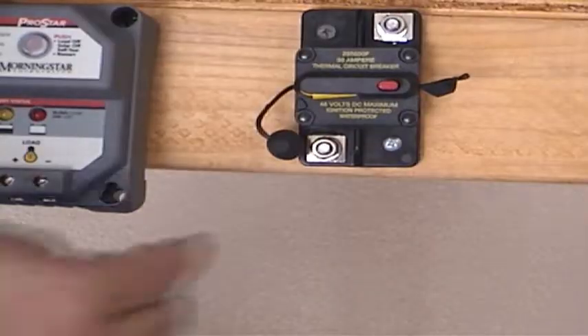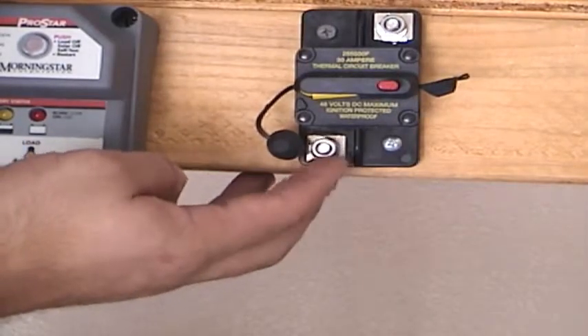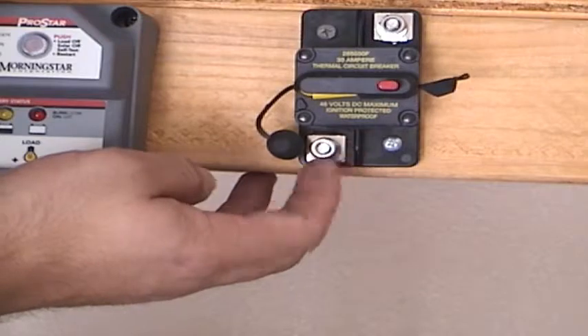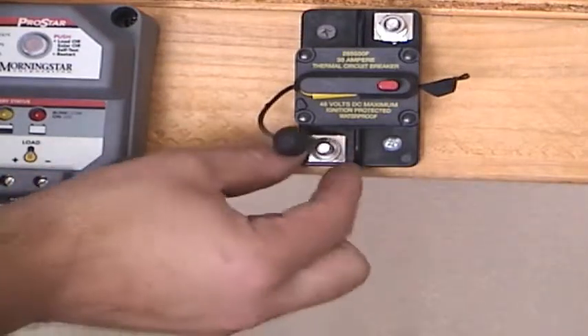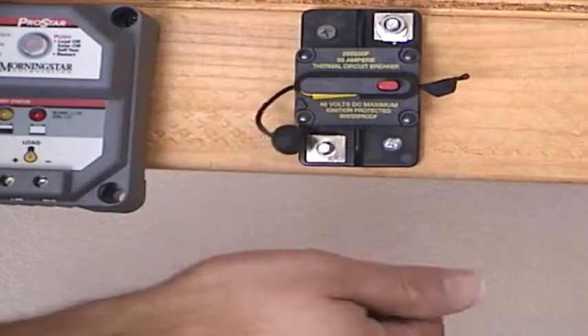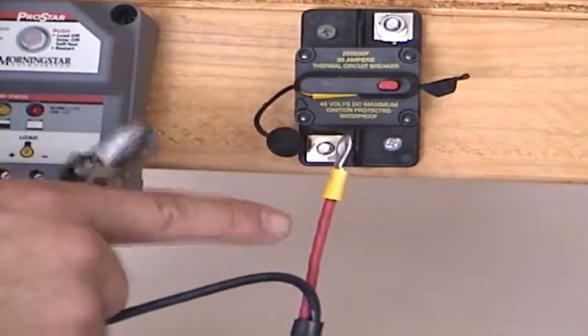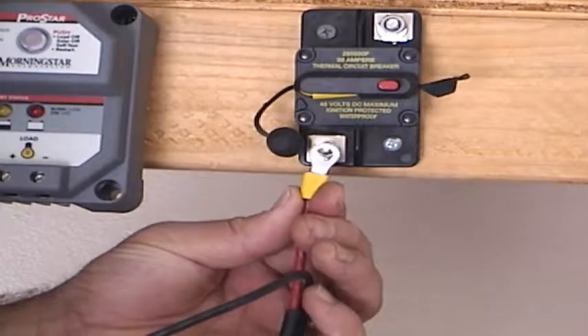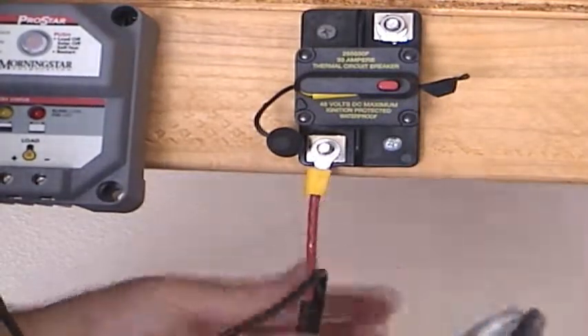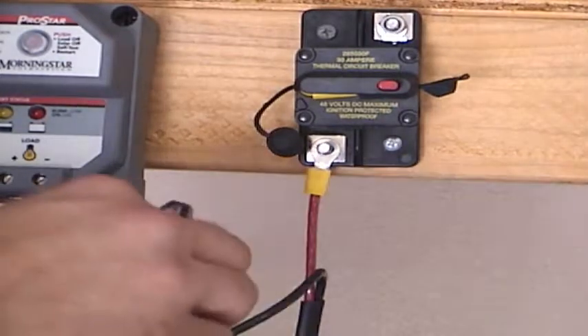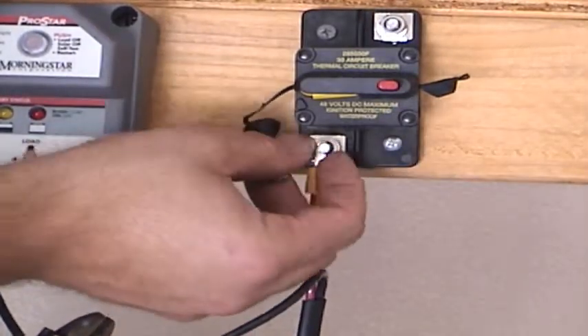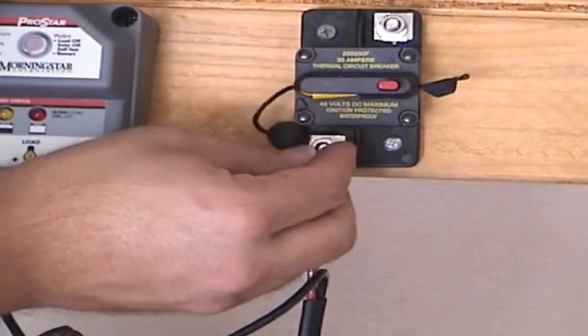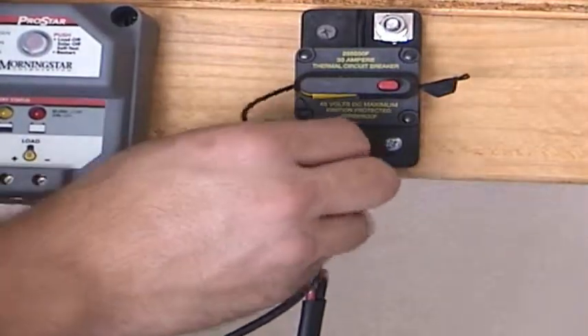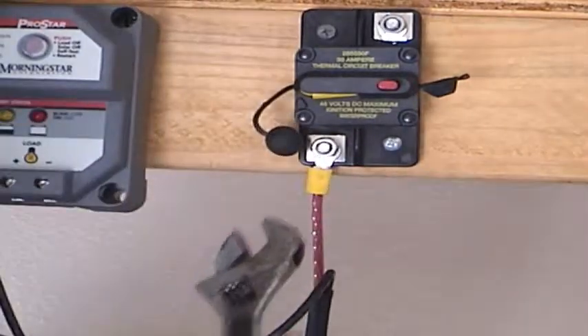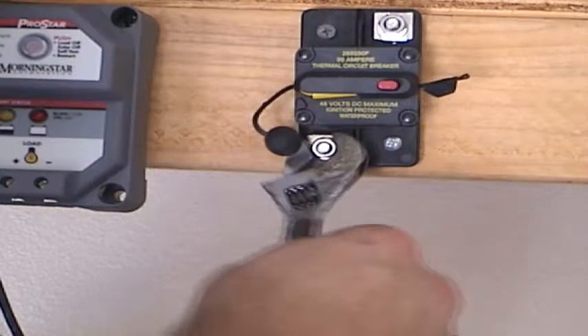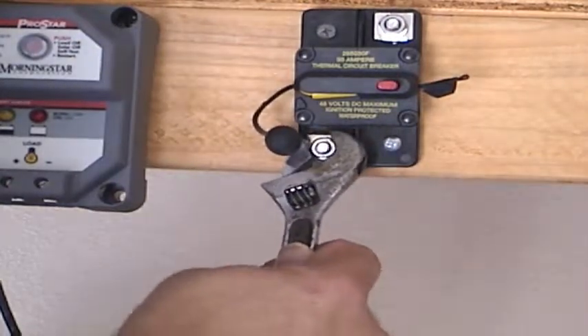Okay. Now we're going to loosen the bottom terminal on the circuit breaker. Remove the nut and the lock washer. And we're going to take the 2-inch tail of red wire and insert the ring terminal over the circuit breaker terminal, replace the lock washer and the nut, tighten the nut down. We'll get our wrench and tighten it down until it is nice and snug.